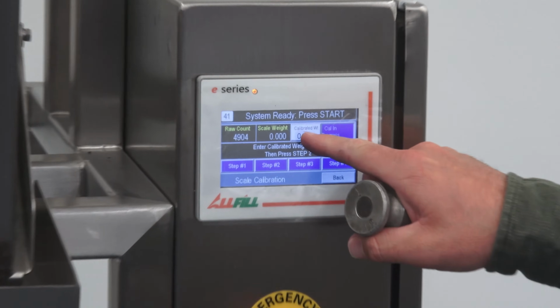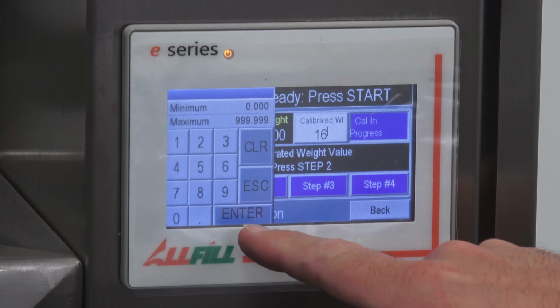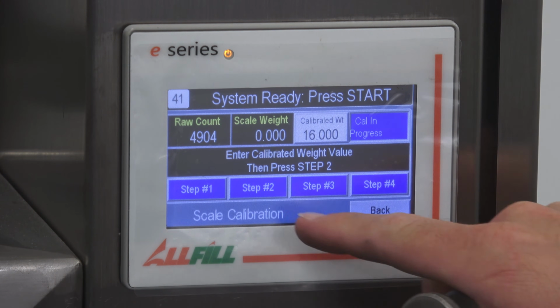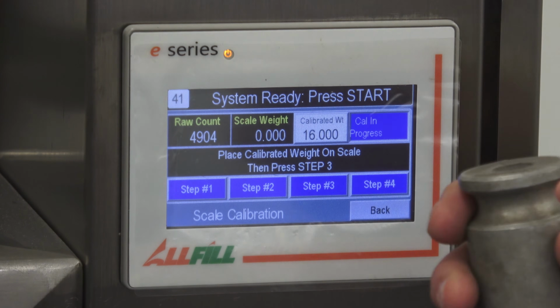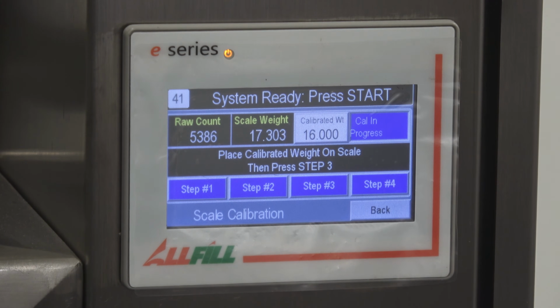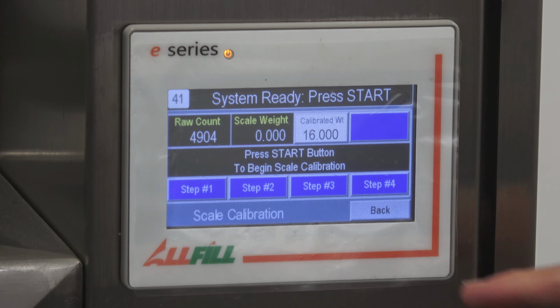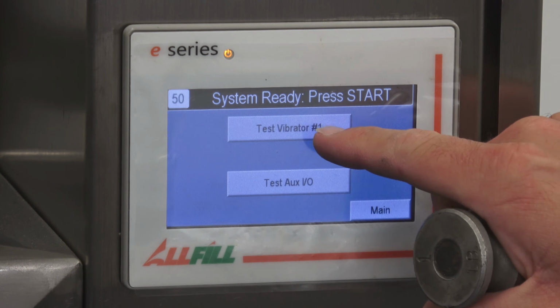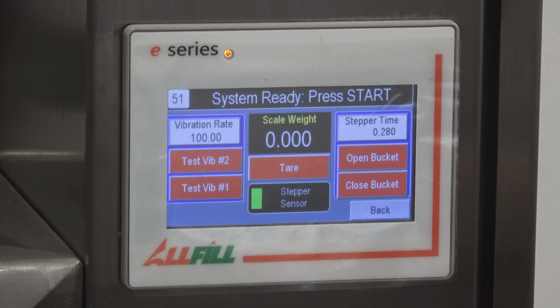So let's go in ounces. I'm going to put 16, enter, and then it says hit step 2. Now you place the calibrated weight on the scale bucket. Wait till your raw count stabilizes, and then you can hit step 3. It says calibration complete, remove weight, then press step 4. And now the scale is calibrated. And if you want to test it, we can go into the test menu, test vibrator, look at the scale, it's tared at 0. I put the 1 pound or 16 ounce weight on it, and it reads correctly.